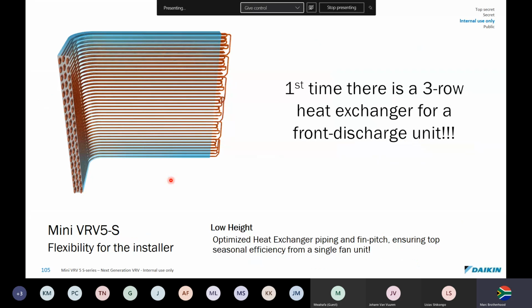We're also a leader in the market. It's the first time in industry that a 3-row coil heat exchanger is being installed for a front discharge unit. You can see there's 3 rows. Optimized heat exchanger piping and fin pitch. Fin pitch is pretty much the spacing of the little aluminium slots. We call it fin pitch. So we ensure that there's optimal seasonal efficiency from a single fan. So there's only going to be 1 fan here, but R32 having the energy it does, we also managed to run slightly smaller condenser pipes, so it increases our overall geometry to give you a bigger heat exchange area for the same sort of footprint.